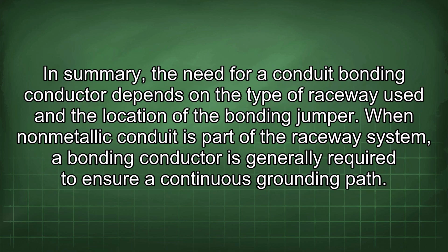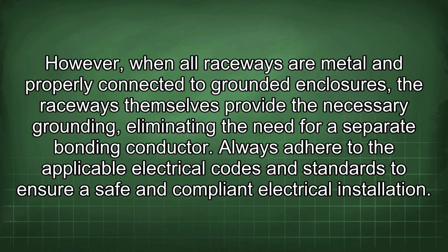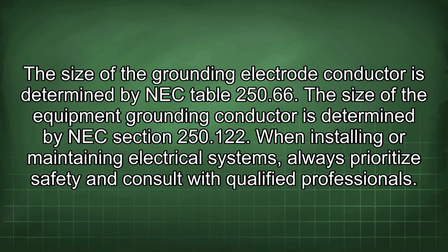In summary, the need for a conduit bonding conductor depends on the type of raceway used and the location of the bonding jumper. When non-metallic conduit is part of the raceway system, a bonding conductor is generally required to ensure a continuous grounding path. However, when all raceways are metal and properly connected to grounded enclosures, the raceways themselves provide the necessary grounding, eliminating the need for a separate bonding conductor. Always adhere to the applicable electrical codes and standards to ensure a safe and compliant electrical installation. The size of the grounding electrode conductor is determined by NEC Table 250.66. The size of the equipment grounding conductor is determined by NEC Section 250.122.